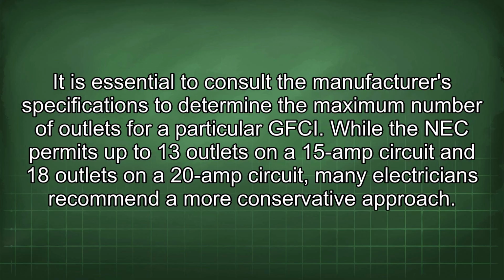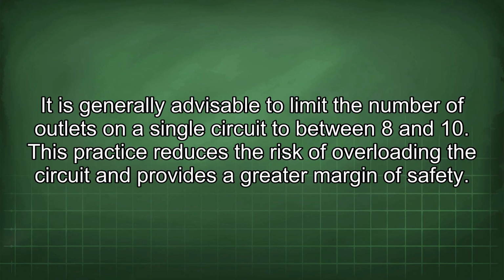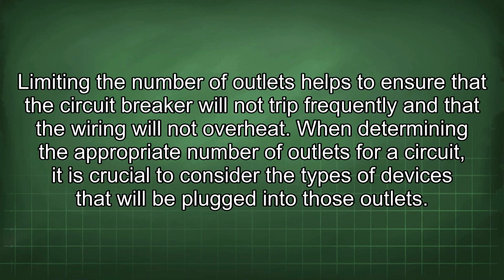many electricians recommend a more conservative approach. It is generally advisable to limit the number of outlets on a single circuit to between 8 and 10. This practice reduces the risk of overloading the circuit and provides a greater margin of safety. Limiting the number of outlets helps to ensure that the circuit breaker will not trip frequently and that the wiring will not overheat.